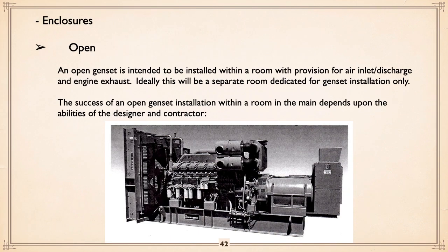Now, with gensets, enclosures: an open genset, as you see in the picture, is intended to be installed within a room with provisions for air inlet and discharge and engine exhaust. Ideally, this is a separate room dedicated for genset use only. The success of that installation depends in the main on the abilities of the designer and contractor. How well is it designed? How good is the contractor? It can be a little fussy.